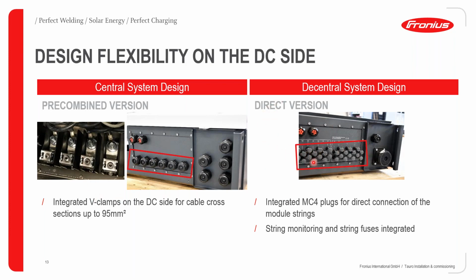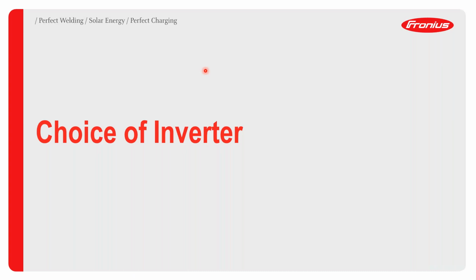And then for the direct version, where you're connecting the strings directly into the inverter, MC4 plugs are provided in the inverter, and all you need for your installation is the connection of compatible MC4 plugs into those provided in the inverter. In this case, when you use a direct version of the Tauro inverter, it means that string fuses will be required, but the additional advantage that you're going to get is that string level monitoring will be possible. And therefore, this is also another advantage of the decentralized or the direct version of the Tauro inverter. Let's now look at the choice of the inverter.